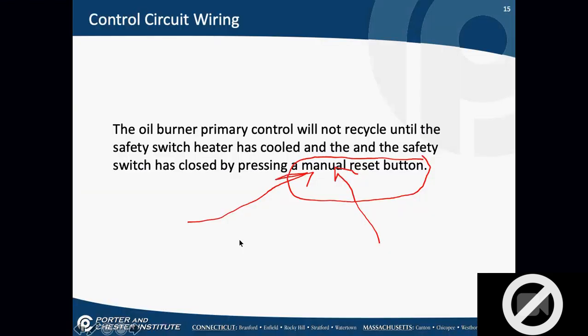Okay, so sequence of operation for an oil burner for a forced air furnace. We can have power to the furnace. Thermostat calls for heat. Closes R to W. Closes the TT on the primary control. Okay, energizes the burner motor, which turns the fuel pump, supplies oil to the furnace. As long as the CAD cell sees light, that flame continues. CAD cell doesn't see light anymore, the burner shuts off and pops the safety switch.